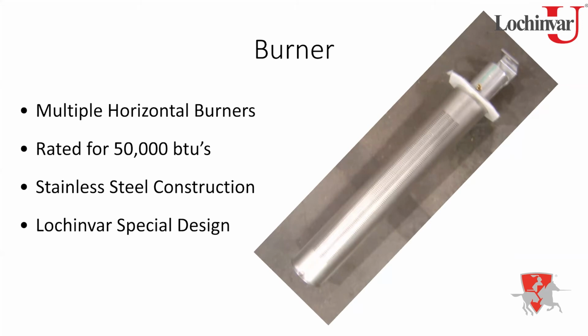But one of the unique things about the burner is that inside the burner, and you can't really see it in this picture, there's what's called a Venturi baffle. This Venturi allows that gas air mixture as it comes in to go down to about the midpoint of the burner, at which point that baffle shoots the gas air mixture down into the bottom of the burner, which allows it to spread out and then come up through the burner ports on the top. So what that does is it gives you a more balanced gas air mixture across the surface of the burner. So it gives you a more even flame.